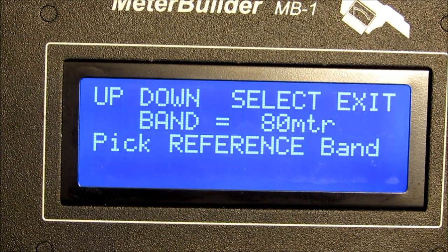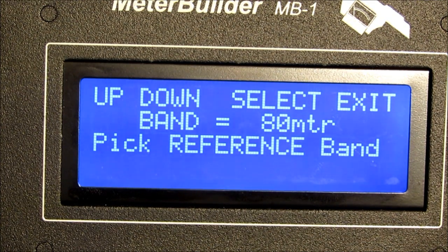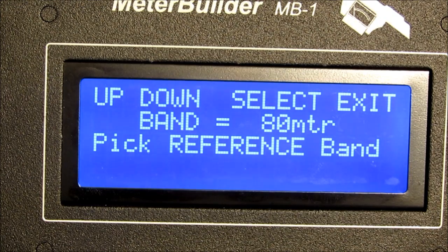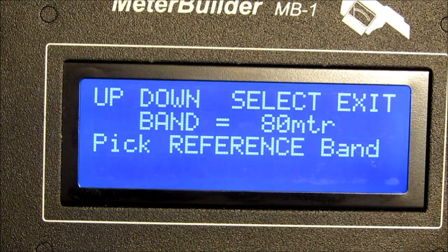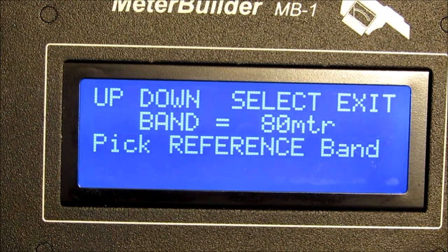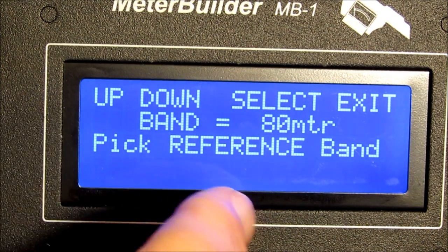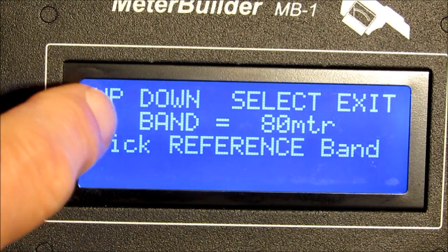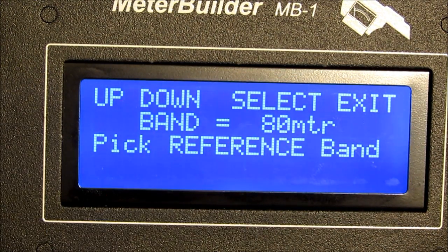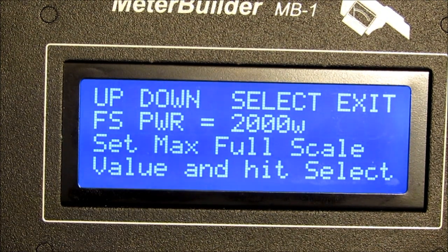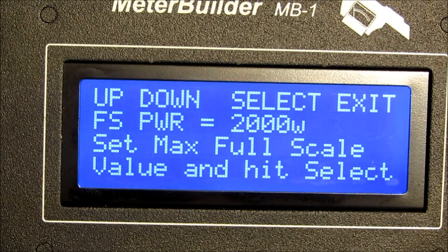This screen prompts us for the band we're using for main calibration. This has importance only if we're going to do band correction — for example, on the 10 meter or 6 meter band, if there's some roll-off compared to the reference band. We'll skip band correction in this demo, but we have to enter the value anyway, since you may want to go back later and add band correction using the edit function, so that number needs to be there. In this case, we're going to use the 80 meter band. If you wanted another band, you could select it with the up-down switches, but 80 meters is fine for our choice. To select, we pick option 1, 2, 3. Okay, so we've picked the 80 meter band.